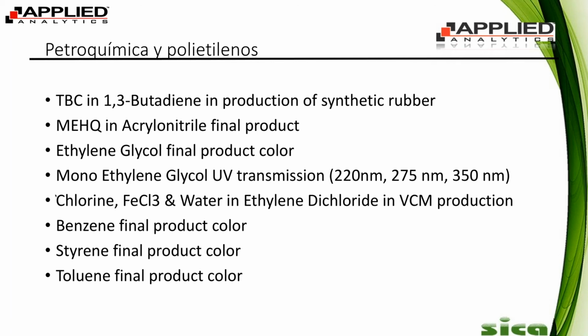MEHQ in acrylonitrile is a good application. Ethylene glycol would be a color application, so that would be a physical parameter like I was talking about at the beginning. That would be the same with MEG, UV transmittance. So we cannot measure MEG concentration as it does not absorb where we need it to, but we can measure the purity of it or the transmittance of it. This is pretty common. It's a very, very straightforward application for us. Like I said, transmittance is just measuring the amount of light that successfully passes through. So there's a little less to it than measuring, say, a chemical concentration.